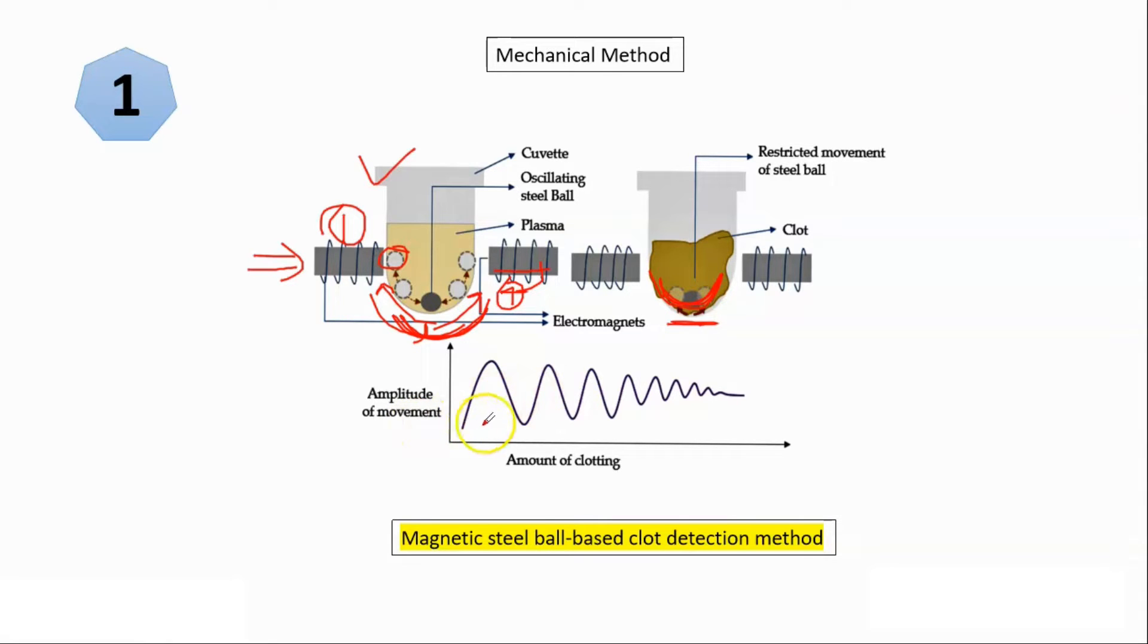So when ball is normally moving, normally oscillating on activation and deactivation of magnets, then clot is like this normal. When range of motion is minimized due to clot formation this will go like this. Here at this point of time chronometer gets stopped as clot is formed. This is how it detects the time for clot formation.